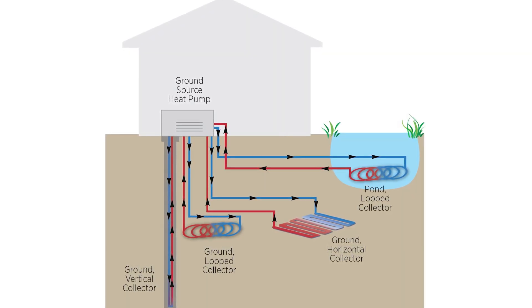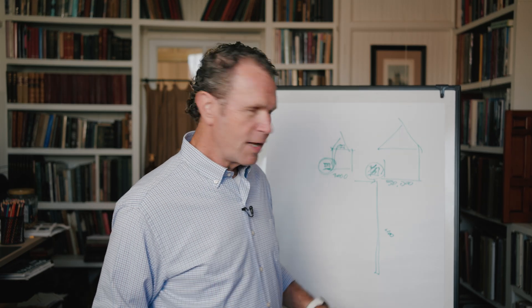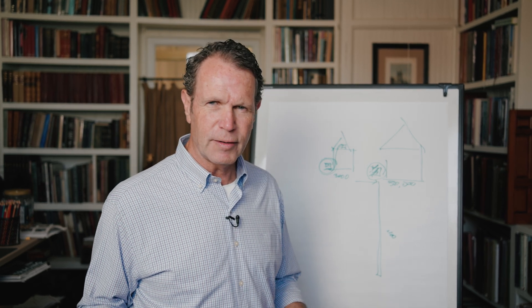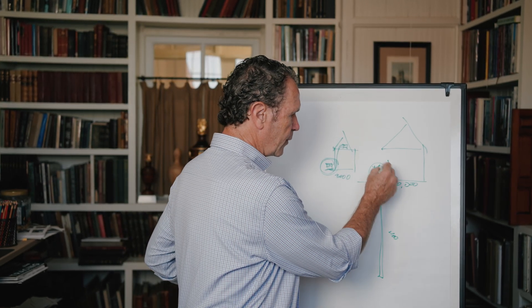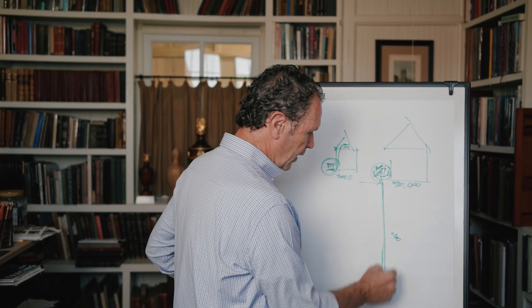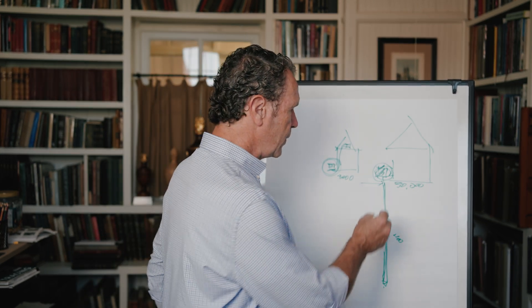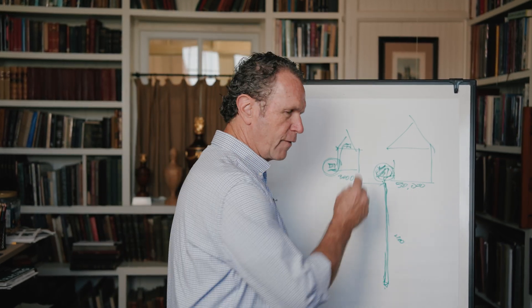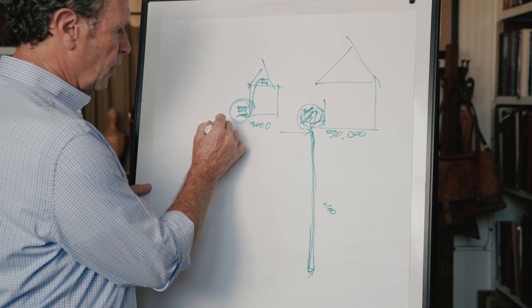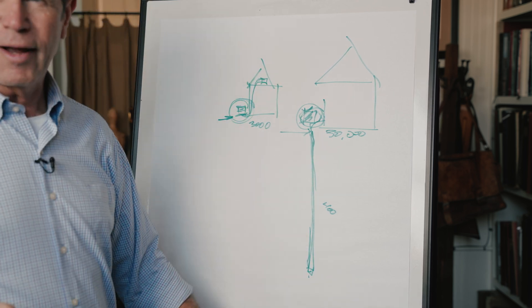On this house we end up drilling holes 400 feet deep, because the earth is a constant 55 degrees temperature. So I can take the heat coming off that refrigeration, run it down into the earth, and by the time it gets to the bottom and comes back up, it's 55 degrees — even though it may be 110 degrees going down. Instead of running electricity to power a fan to cool things, we just run it into the ground.